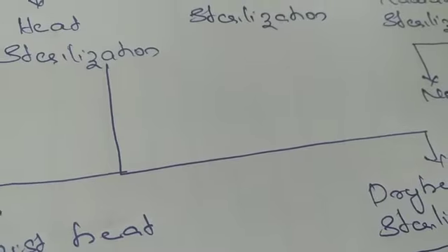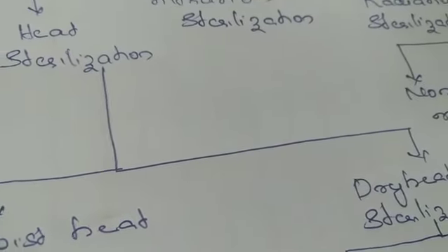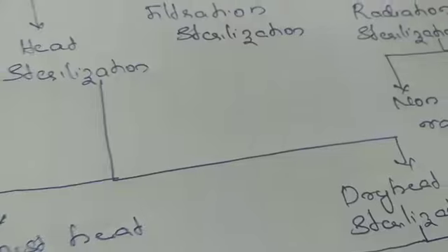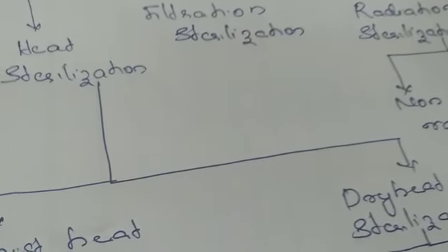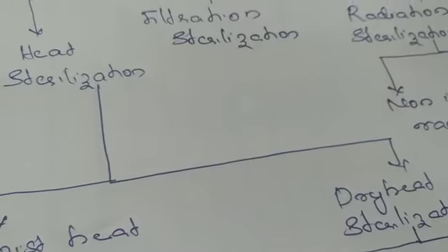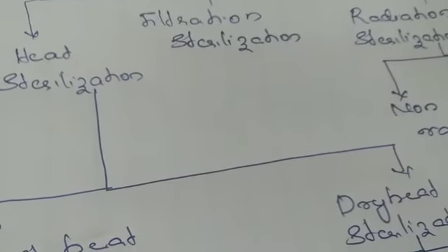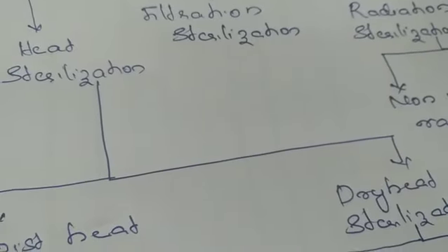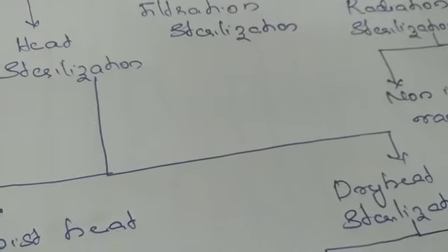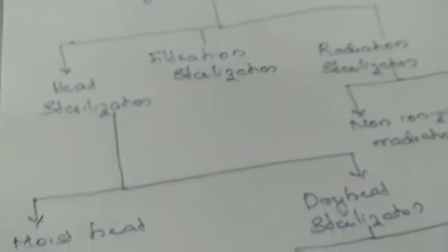In both sterilization processes, it is important that the temperature of the material to be sterilized must be raised to the sterilization temperature. This involves the heating up stage. The duration of time for which the load is exposed to the sterilization temperature after attaining the heating up stage is called the holding stage.